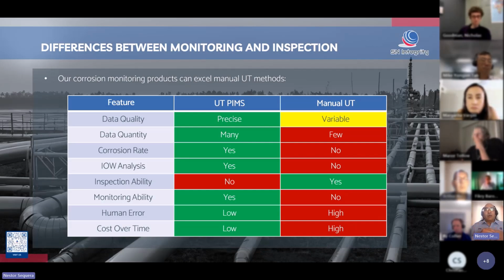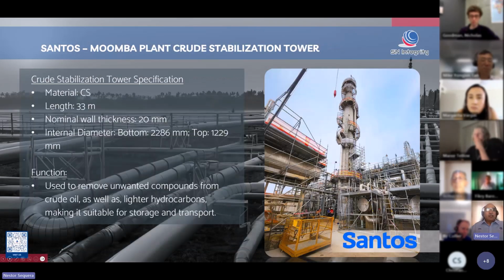But the way we should be doing monitoring is we go and do inspection manually, and whenever we find an issue that needs monitoring, then we use the permanent installed monitoring sensor. It's pointless to go manually doing that because it's a time-consuming exercise and we are not very good at repeating tasks. Plus the error is too high when we are repeating and trying to get accurate values to predict corrosion rates. So now let's get into our case.